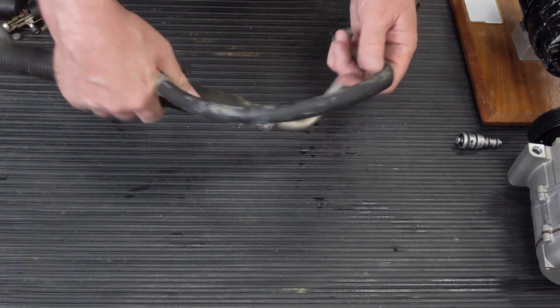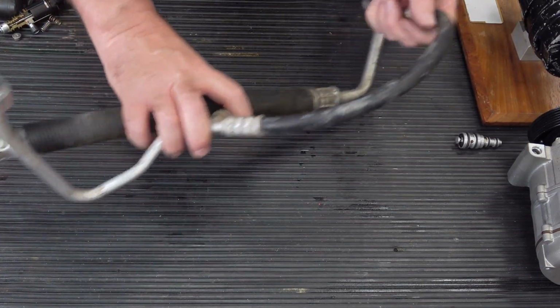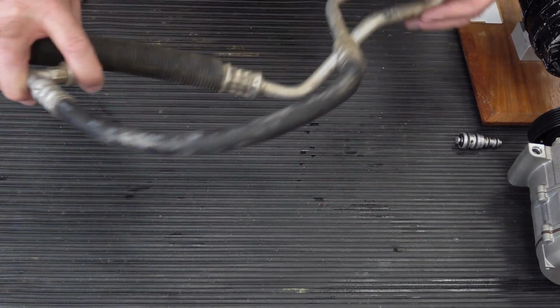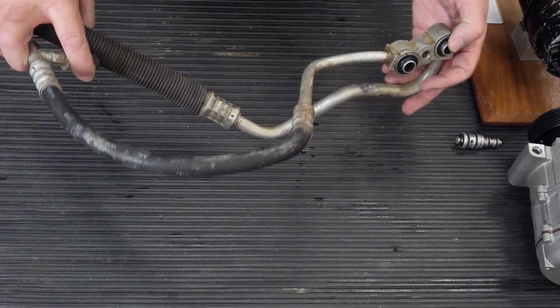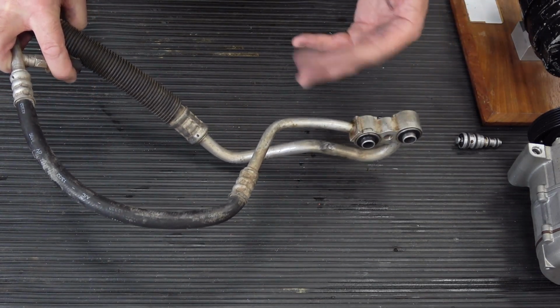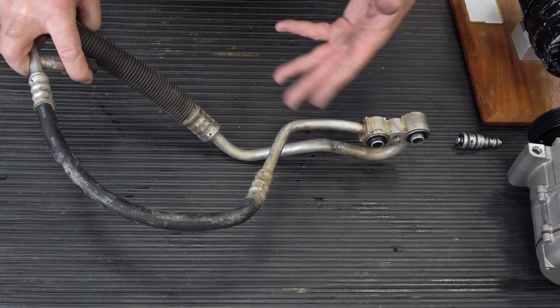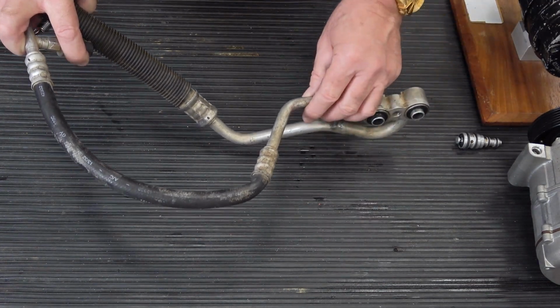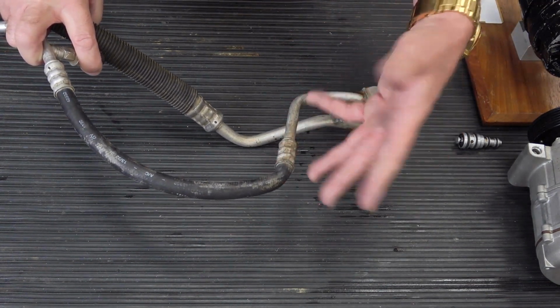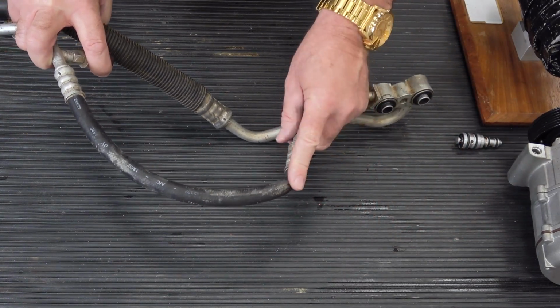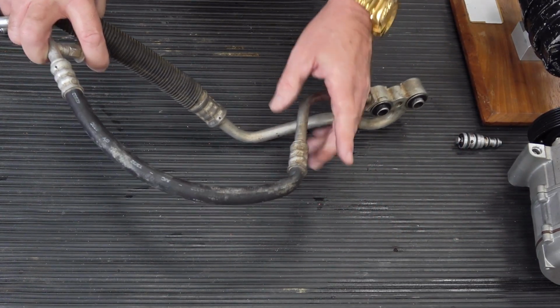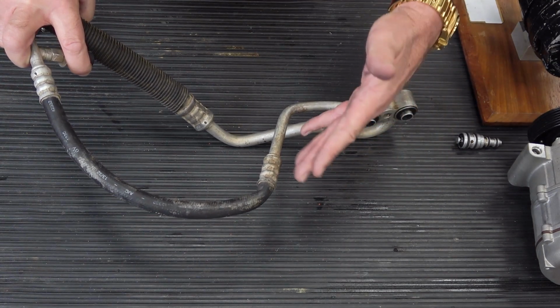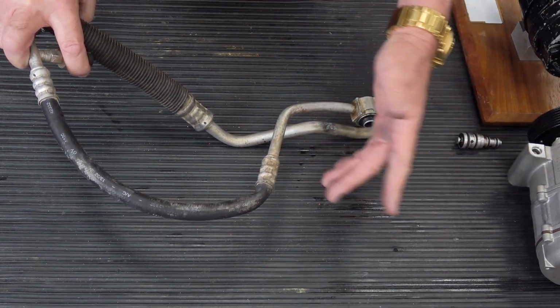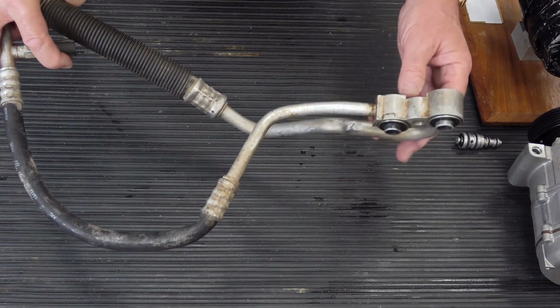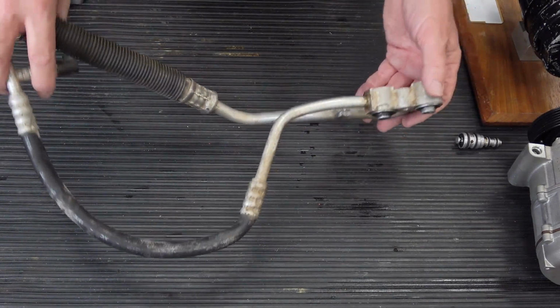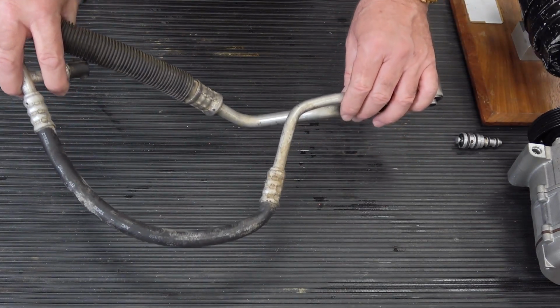And of course this particular hose set has at least four different hose-to-metal, rubber-to-metal crimps. So in my experience, when you count the cost of flush, your time to do the flush, the fact that you're often flushing an 8, 9, 10, 15-year-old hose that you don't even know if it's leaking yet, if you add up the cost of flush, your time to do the flush, and compare it to the cost of a new hose assembly, it is often literally cheaper to replace hoses than to flush them.